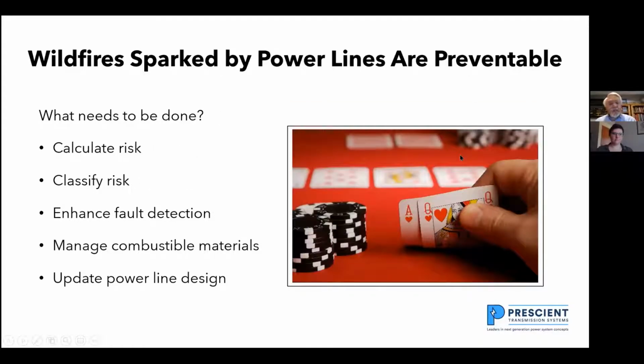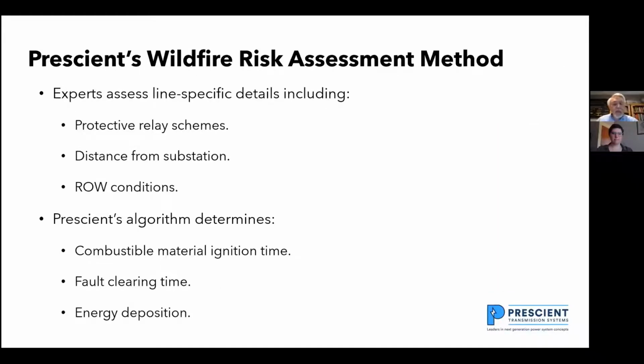So what needs to be done? Well, you have to calculate the risk. You have to classify the risk. You have to enhance fault detection. You have to manage combustible materials, and you have to update your power line designs. When we're looking at a wildfire risk assessment, we look at your protective relaying schemes. We look at the distance from a substation, and we look at right-of-way conditions. We've developed algorithms that give me combustible material ignition time, and that combustible material ignition time is a function of fault clearing time and energy deposition.